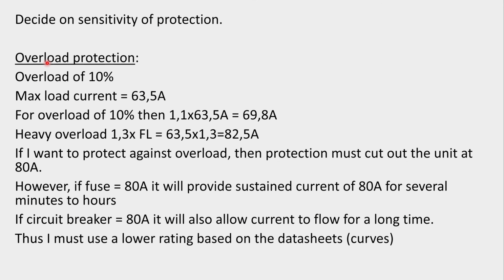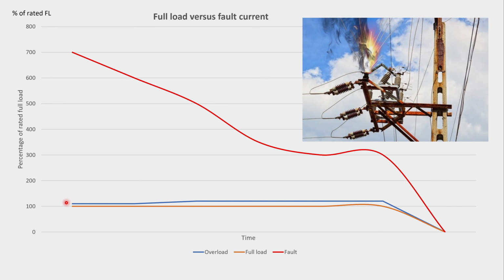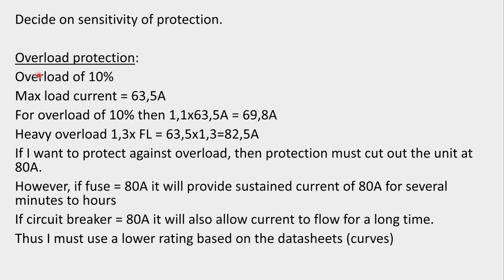So the inverter does have its own internal protection. So that's very important, because then I can determine if I'm protecting for just overload or am I protecting for faults. Recall earlier that overload is just a little bit higher than the maximum load current, whereas a fault is a much higher multiple of the maximum current. All right, so let's critically evaluate this. Let's call it overload protection. And it's a heavy overload of, say, 1.3 times the full load current, 82.5 amps. So if I wanted to protect for a 30% increase in the full load current, so that would mean 82.5 amps. So let's just call it 80 amps.